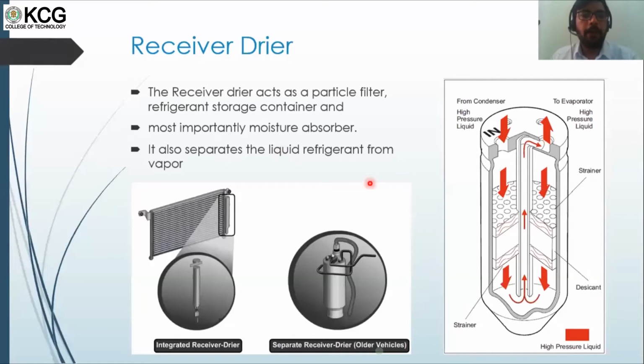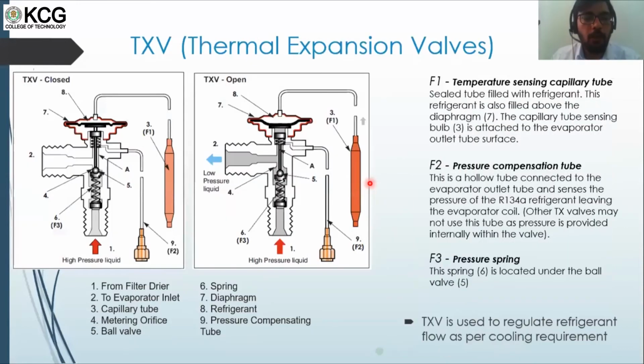Okay. So now we have a completely liquefied refrigerant at high pressure, which is traveling to the TXV. So the TXV, I'll try to explain a little bit. This section which you see here, this is the sealed refrigerant tube. This is not attached anywhere. This is a sealed tube filled with refrigerant. So mostly this tube will be attached to your evaporator.